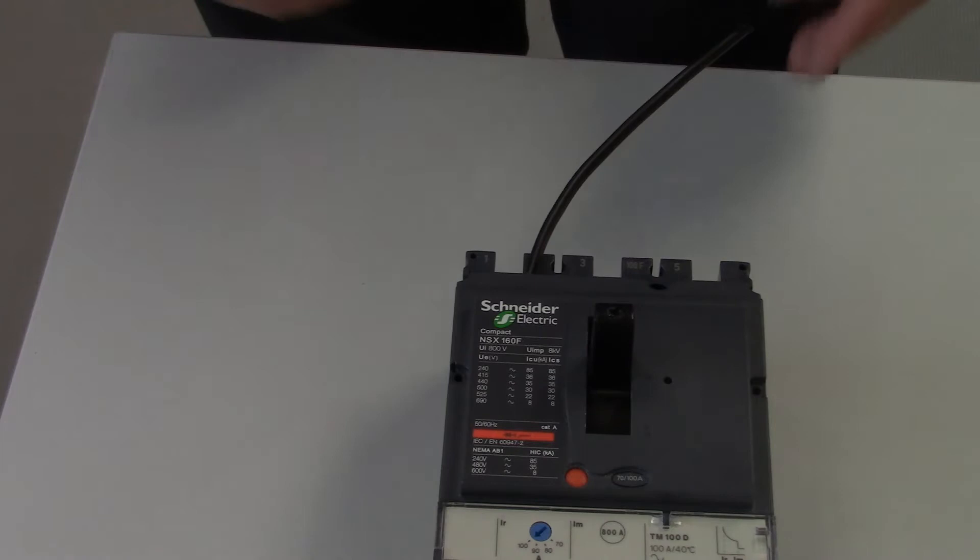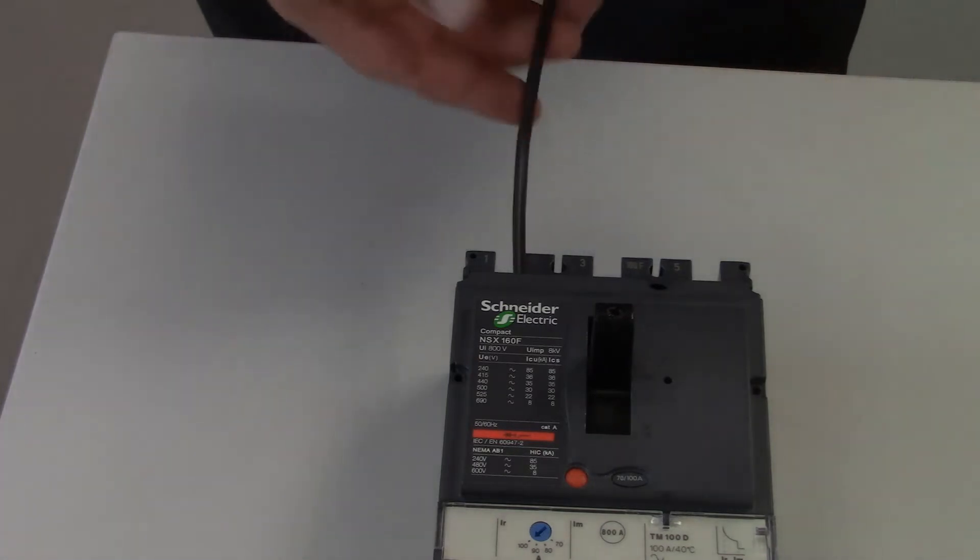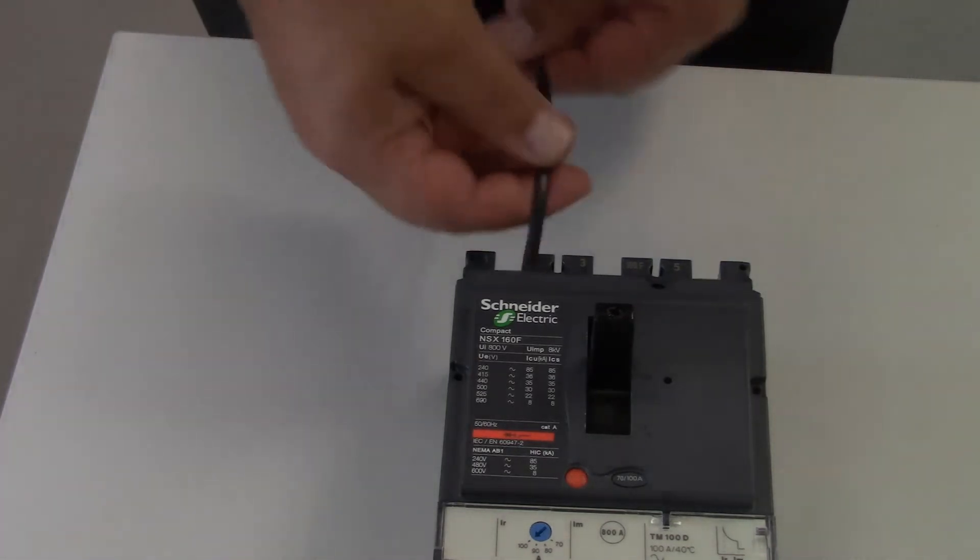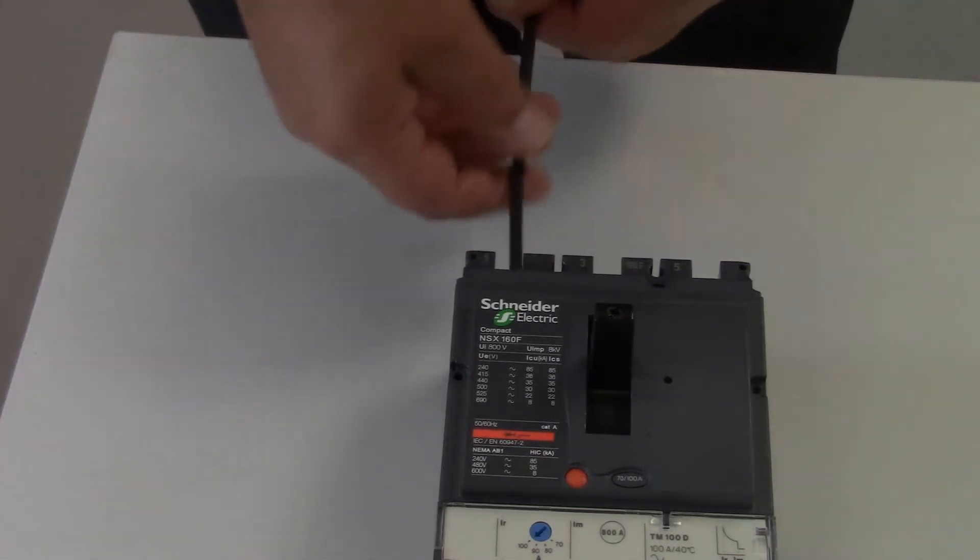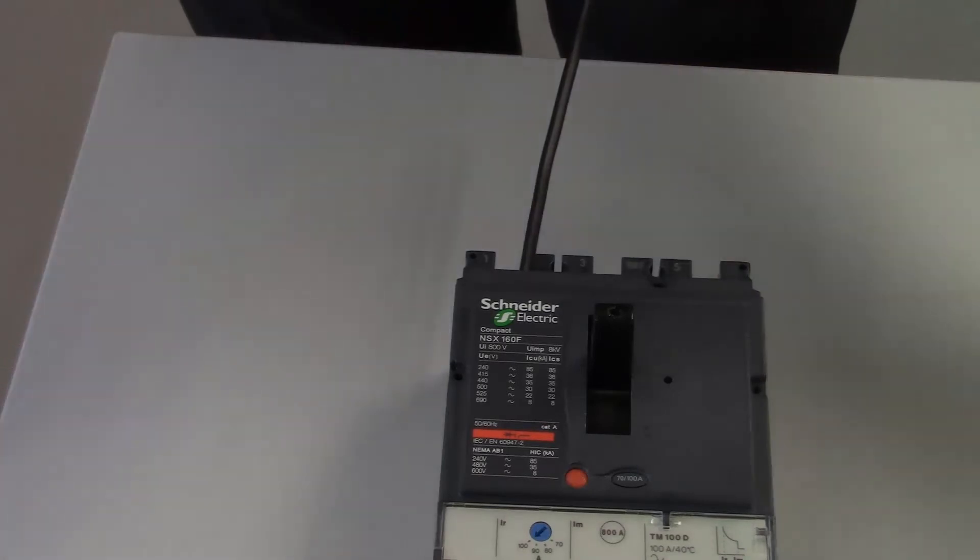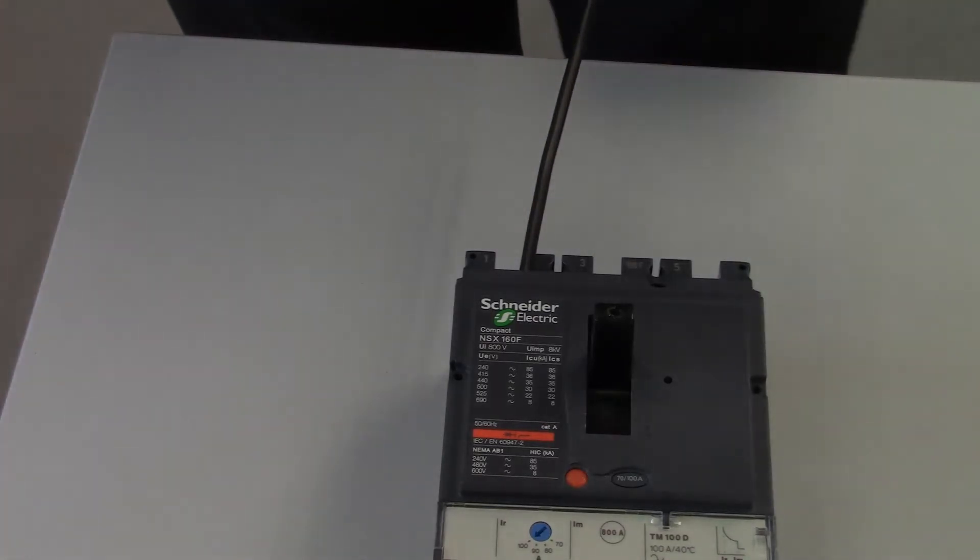The first telltale sign will be the cable here sticking out the top. That would indicate that there is something extra inside this breaker.